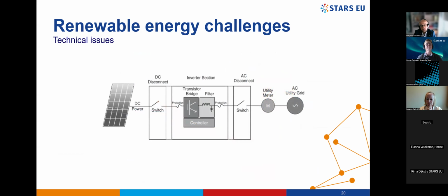In the case of renewable energy, in particular photovoltaic power, these are not rotating machines. They use power electronics that actually take the frequency of the system to replicate it and feed in directly. This system is called an inverter. It converts DC power to AC power, and this is called grid-following, because the grid must give the frequency and these devices just copy it.